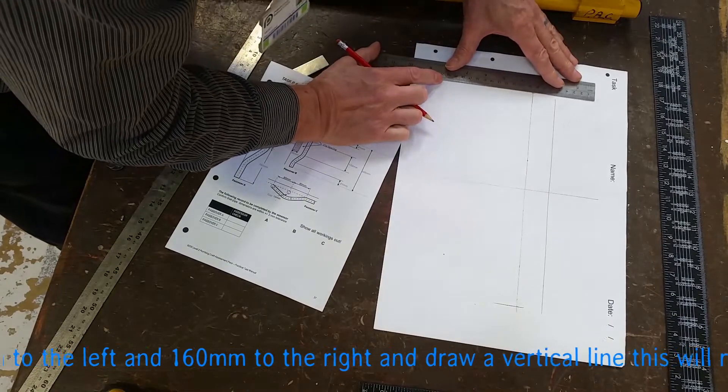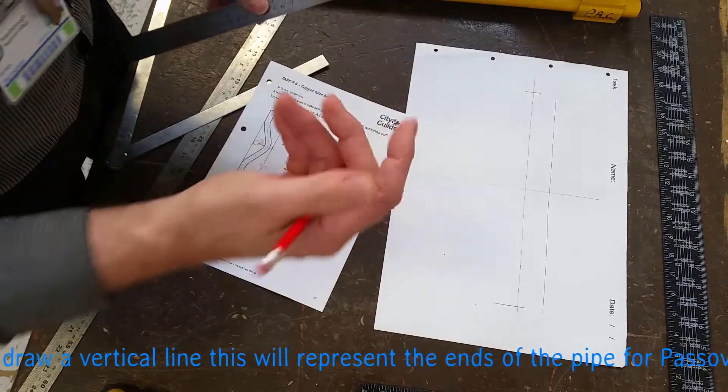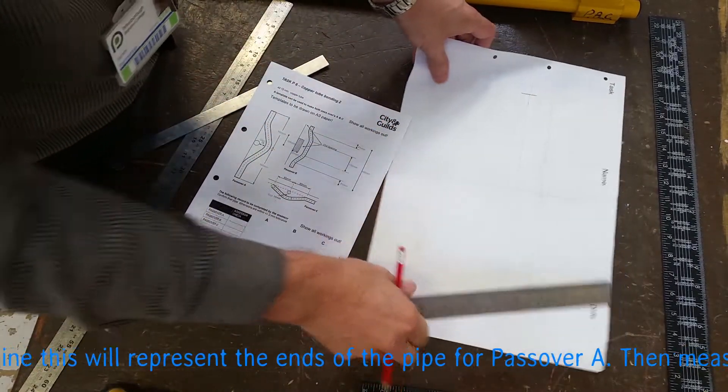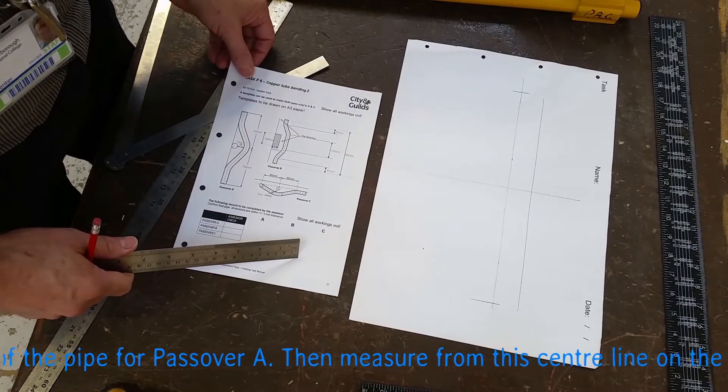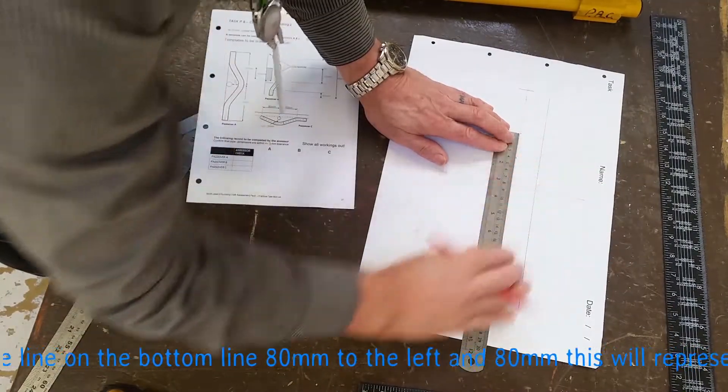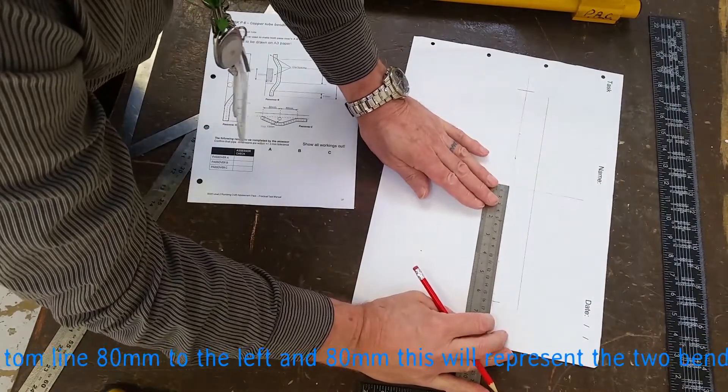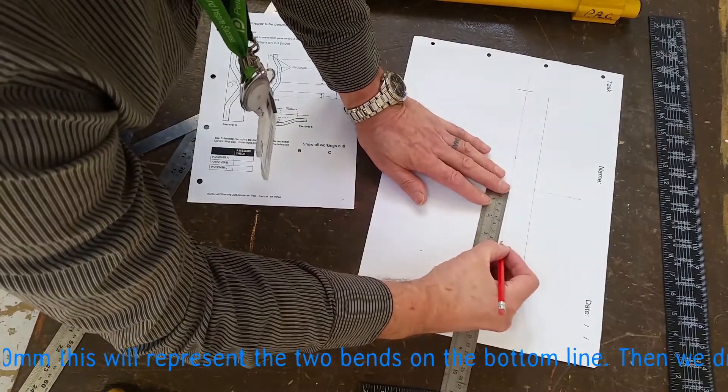This helps to see if your pipe is accurate to the drawing, because later on we're going to lay the pipe with bending on there. So the next two measurements we need are for the second two bends on the bottom pipe, which are 80-80. So we measure from the center line on the bottom line, 80-80, and then draw the line through, so it goes through our top bend, joining up our bottom bends to our top bend.